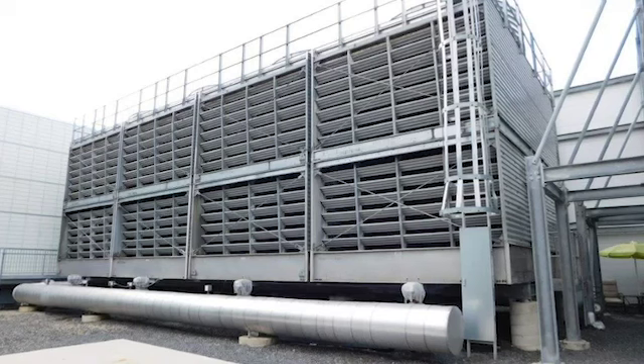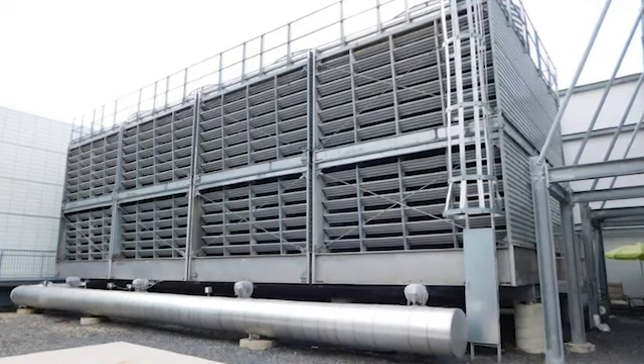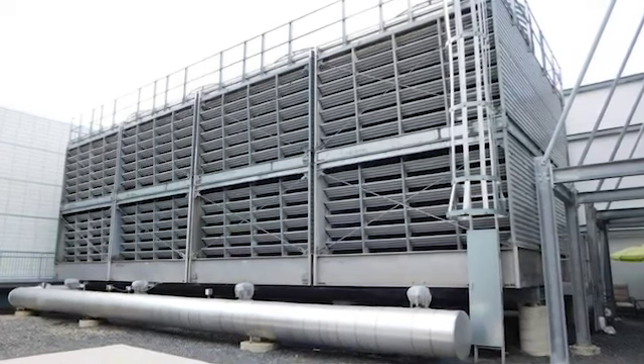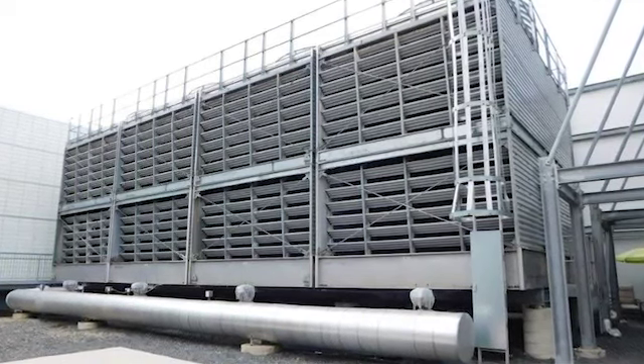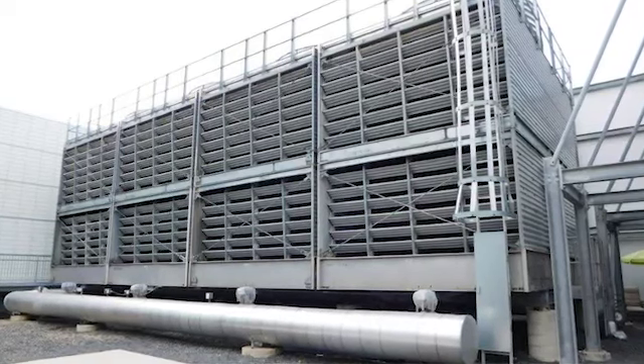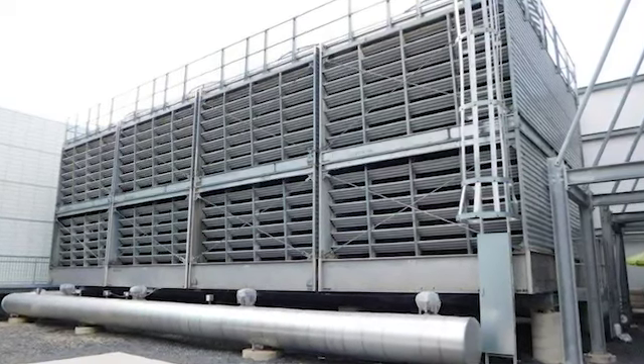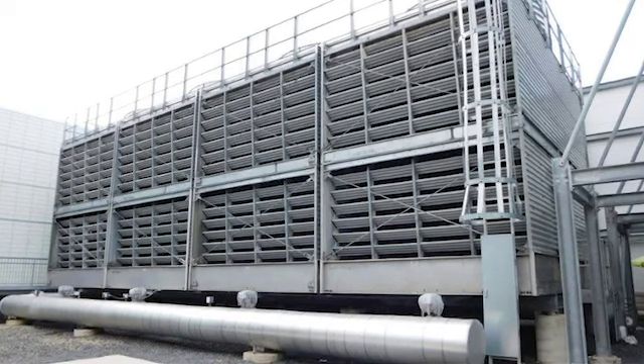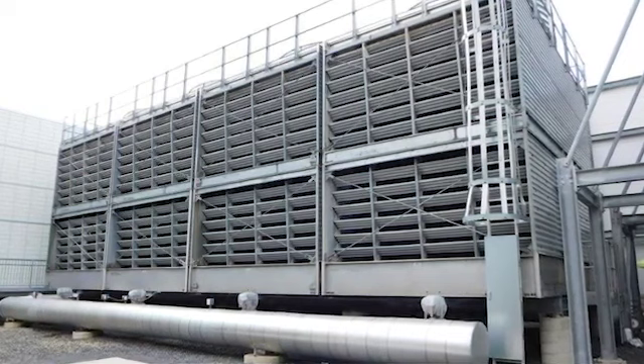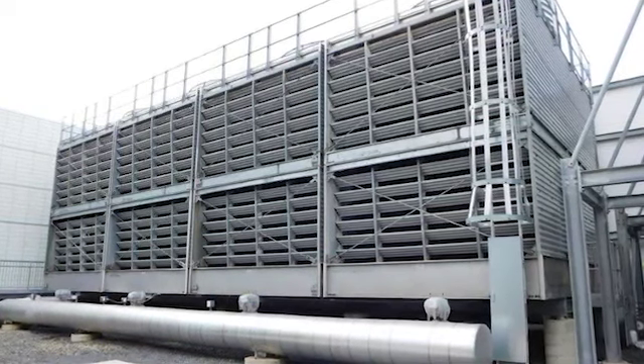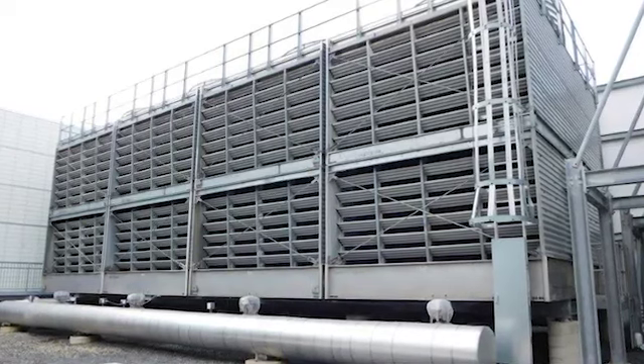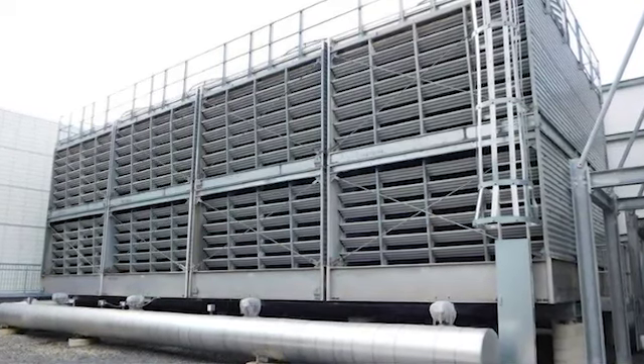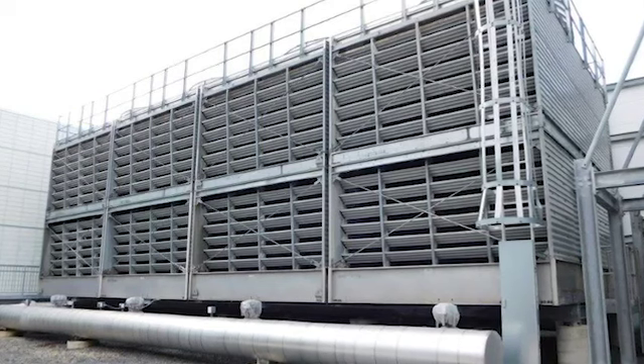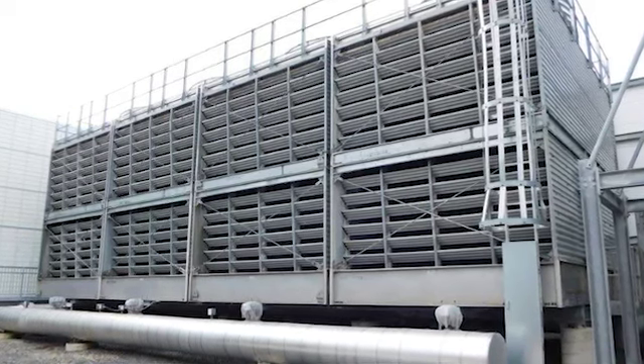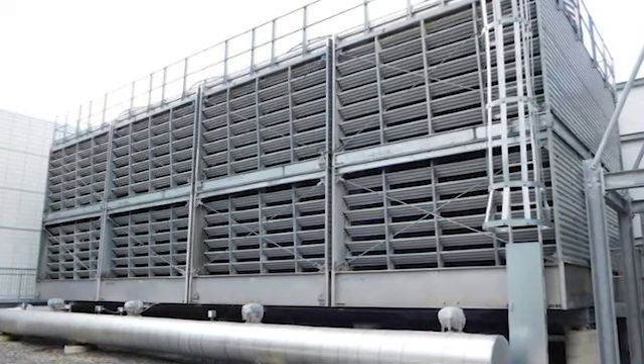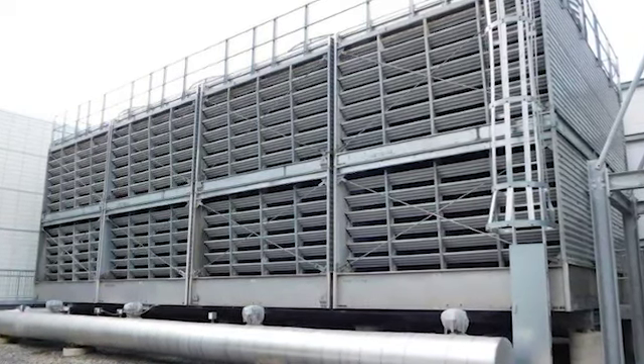We have ultra quiet fans on this cooling tower array that takes care of our chillers downstairs. Of course, we're extremely sensitive to Legionella, and so we do Legionella testing every 2 weeks. We report to the EOC committee in the hospital. And again, just as if we were a department, we send those results. We have an extremely tight Legionella protocol. We disinfect with hydrogen peroxide, in addition to running an oxidizing and non-oxidizing biocide scheme to keep the tower nice and clean. Typically it looks like a swimming pool when we're running it.